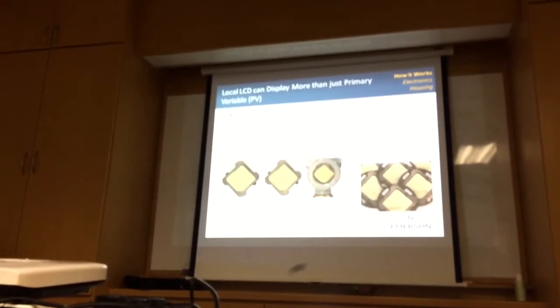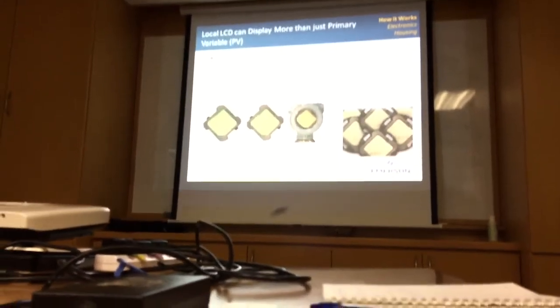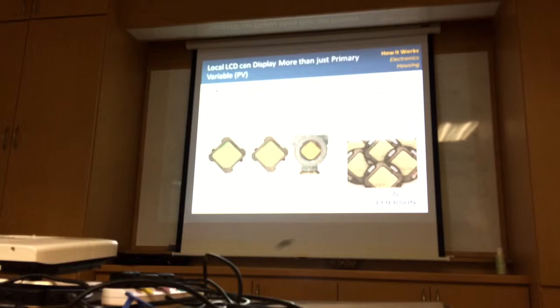Display? That's the next question. Many customers have requirements on what is shown on the display. This is pretty much everything. Our LCDs can display diagnostic information. It can show the settings that you have done to it, which is the PV, the analog output readings, and the alarm settings. Everything will be shown on the LCD when you start up the transmitter. Then it is able to show you sensor temperature, engineering units, percentage of range, bar graph. This is all the information.